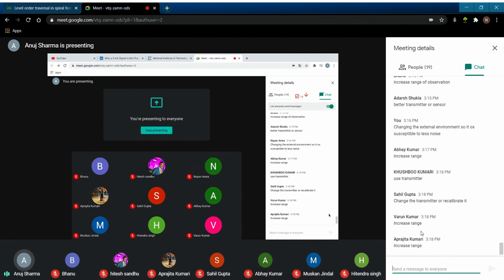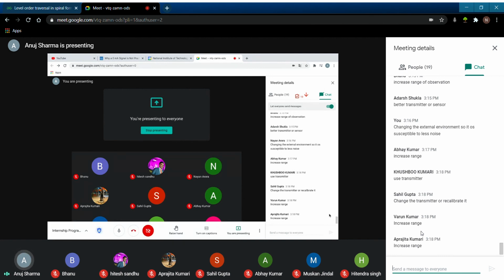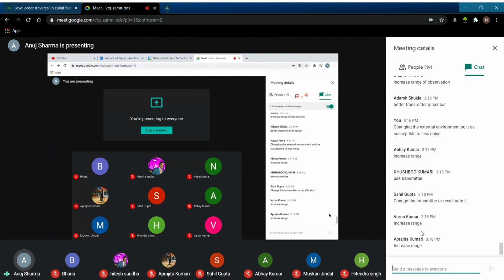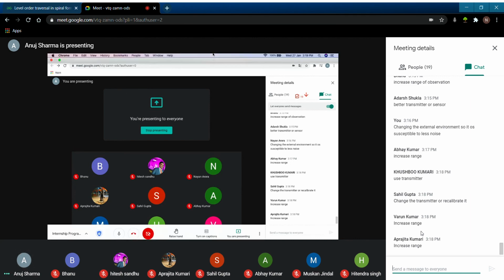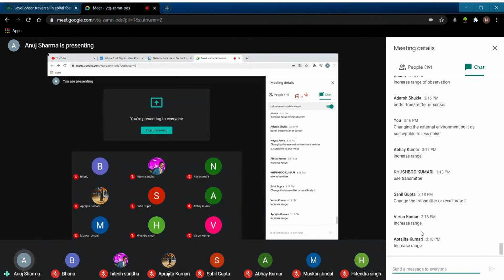So now what he was saying was that it is very important for you to understand that you need to utilize the full range, 4 to 20 milliamperes. In order to utilize that, you can change your receivers, you can change the resistance of the receiver by changing the parameters. You have your transmitter, and you can increase a certain amount of load to get into that particular range, or you can increase the excitation, processing, or amplification of your sensor through your transmitter. This can be the reason for that.